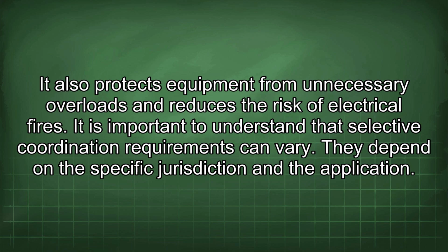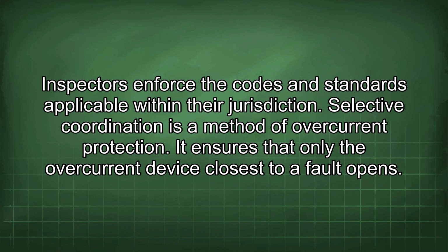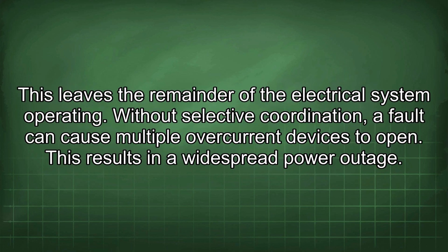It is important to understand that selective coordination requirements can vary. They depend on the specific jurisdiction and the application. Inspectors enforce the codes and standards applicable within their jurisdiction. Selective coordination is a method of overcurrent protection. It ensures that only the overcurrent device closest to a fault opens. This leaves the remainder of the electrical system operating. Without selective coordination, a fault can cause multiple overcurrent devices to open. This results in a widespread power outage.